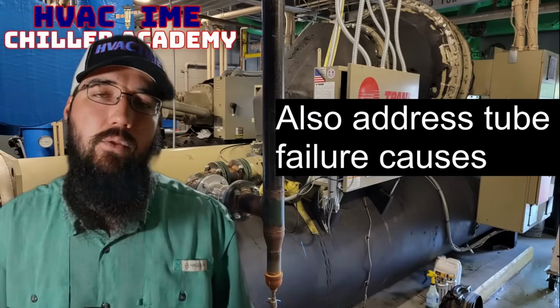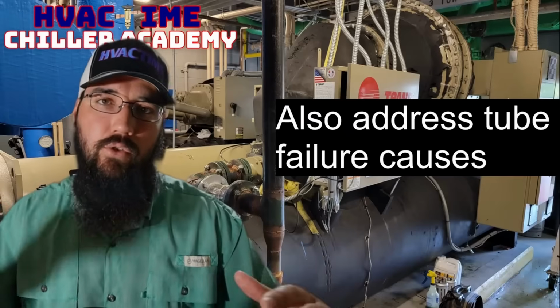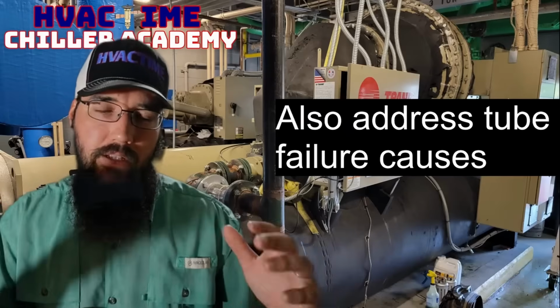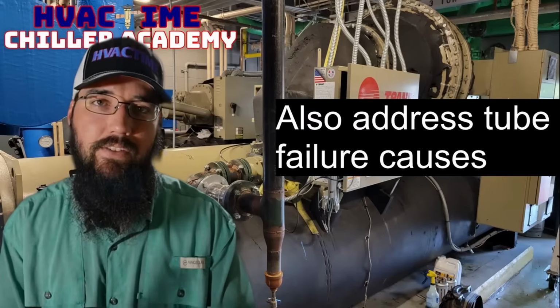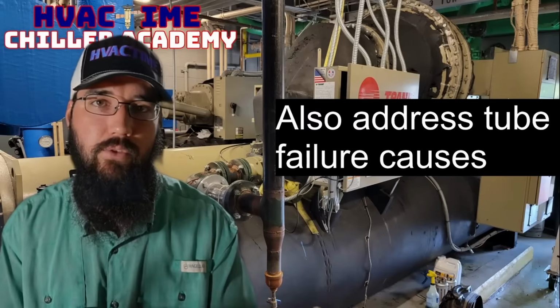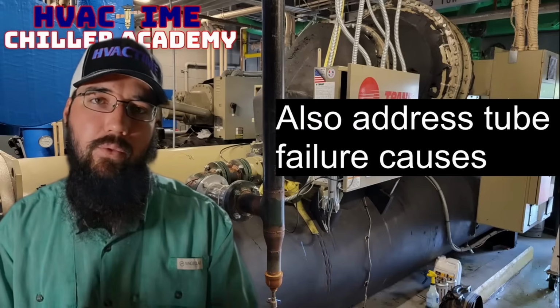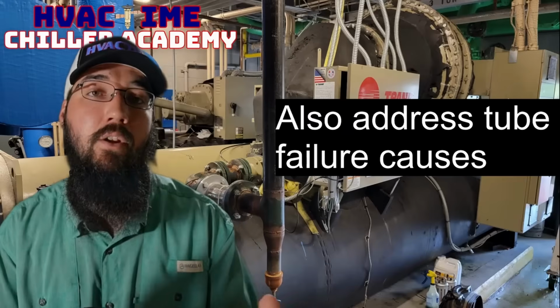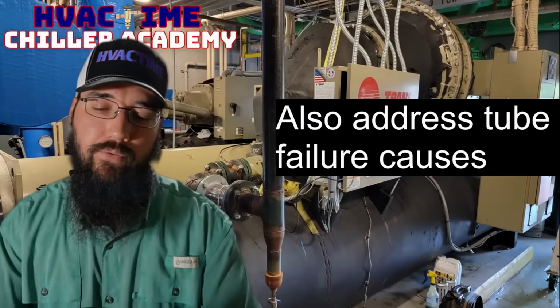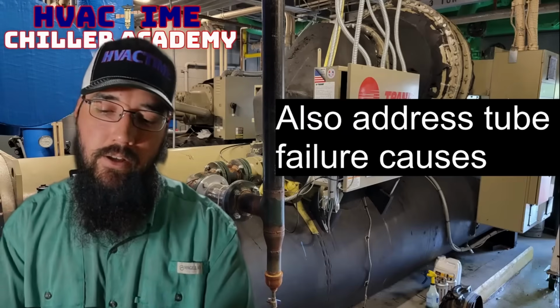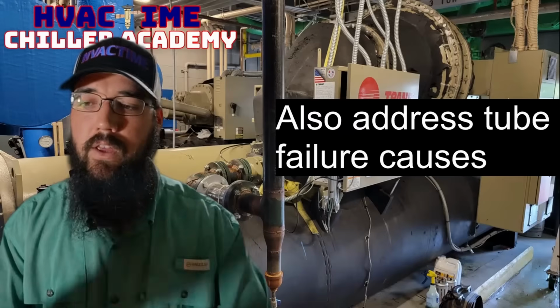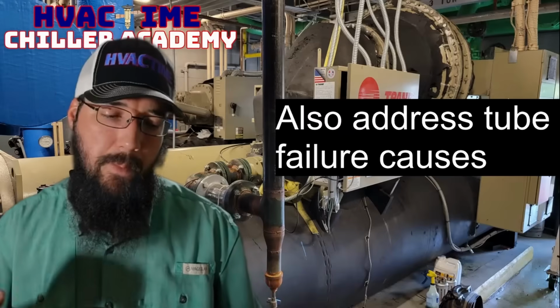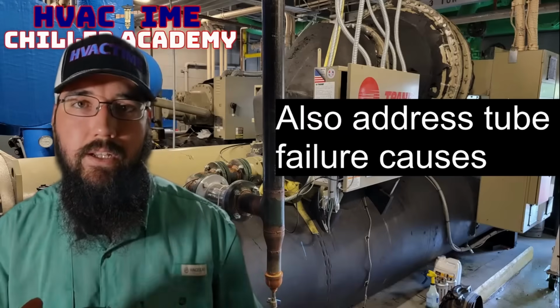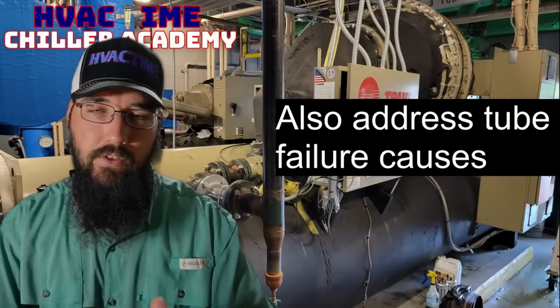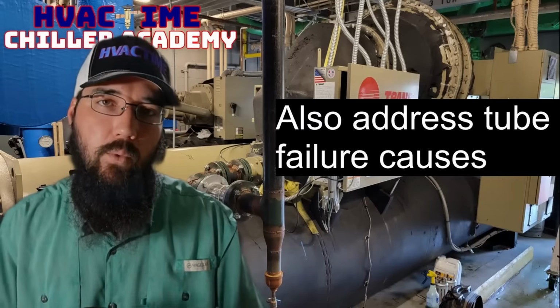Another one would be saddle wear. So these tubes that are going through the heat exchangers, they're sitting in a set of racks, if you will, let's call it that. And these racks can end up becoming a rubbing point, depending on refrigerant conditions, depending on flow conditions, water flow. And I'll give a really clear example of this, the subcooler rack for a YK.